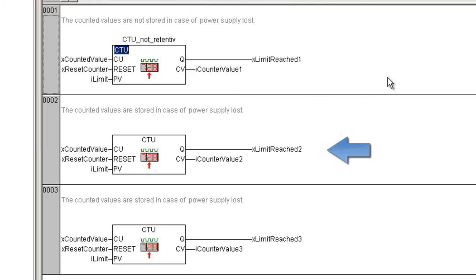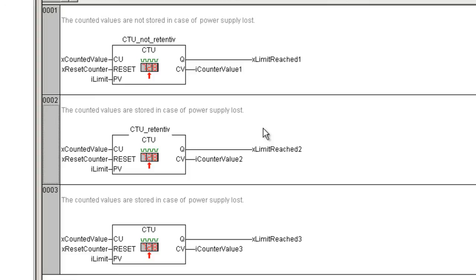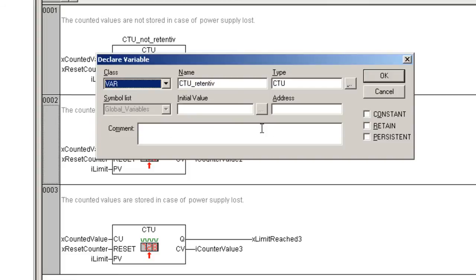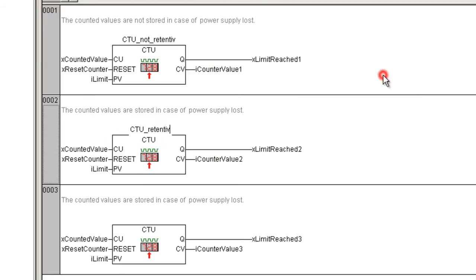In the second counter the status should be buffered. We will create a retain and persistent variable for this instance. Let us call it CTU retentive and be a local variable from type CTU. Now we activate the options retain and persistent by setting the checks in the appropriate fields, and confirm the declaration with OK.